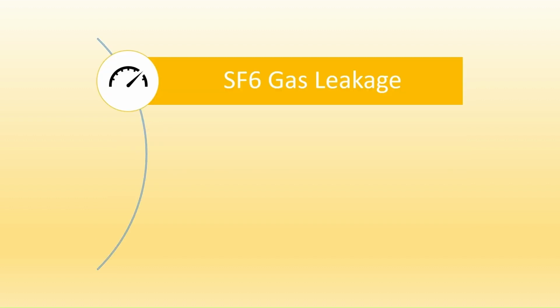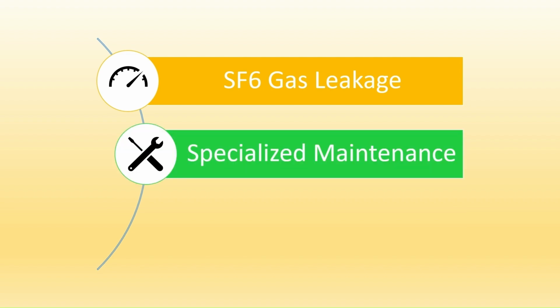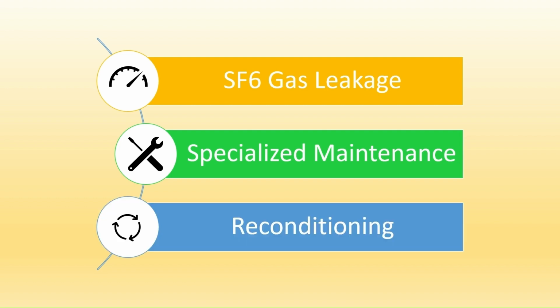SF6 gas can leak from the breaker, potentially creating an uncomfortable environment due to its density. Handling and maintenance of an SF6 circuit breaker requires specialized training to prevent leaks and ensure safety. SF6 gas needs to be reconditioned after each operation to remove impurities and maintain its insulating properties. Due to all these disadvantages, in future, vacuum circuit breakers can capture the high voltage market. This is about the SF6 circuit breaker.